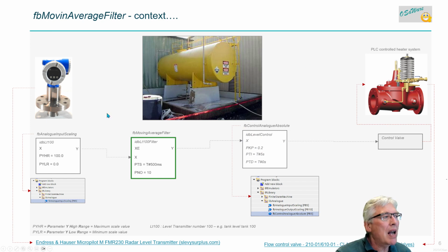It goes to a control valve, and then we have some level metering here in the tank, where we use another function in the template, scale analog input. And here it could be a scale analog output, but this level controller has a number format we use, 4 to 20 milliamps, for the control valve, for instance.